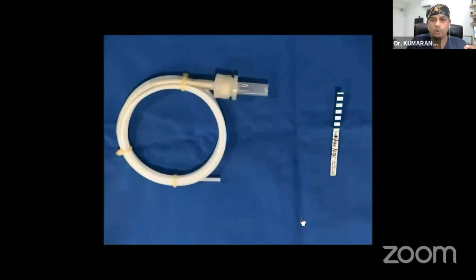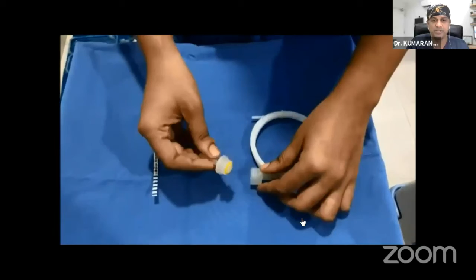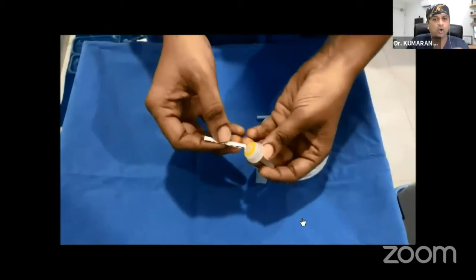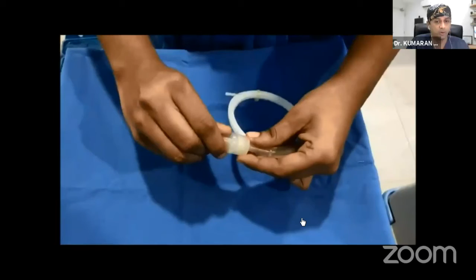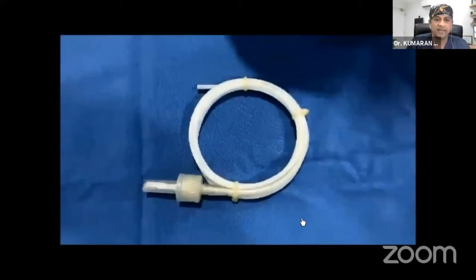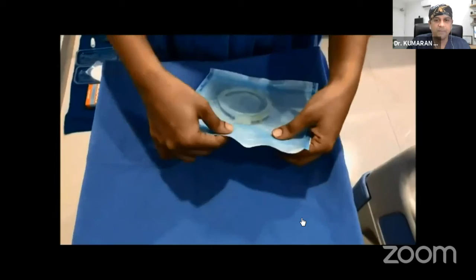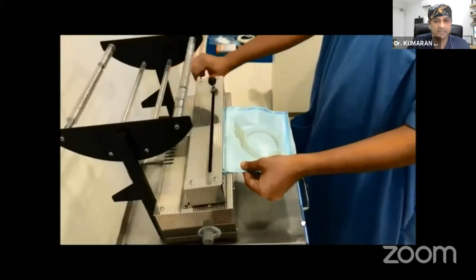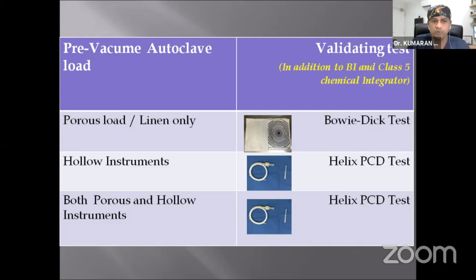The class 6 indicator is very important whenever you have a hollow instrument. The most important thing, and the common mistake done here, is the way you fold the indicator. The indicator has to be folded inwards as shown here and not outwards, because most of the time if the indicator is folded outwards, the test is positive even with the initial autoclave cycle before it gets completed. Then this should be packed as shown here. Make sure you use a medical grade sealant to close this, which is about 3 centimeters in length, and then it is autoclaved. So this is how the class 6 indicator should be used.